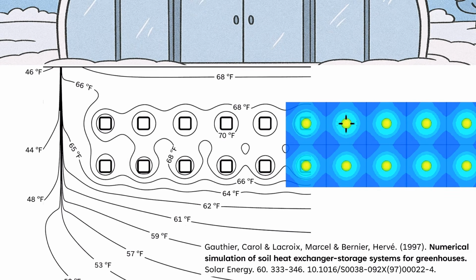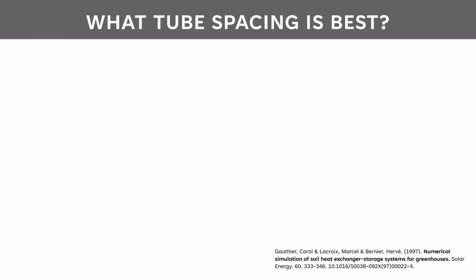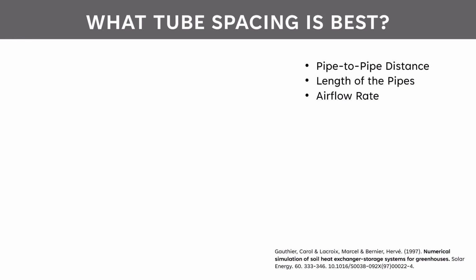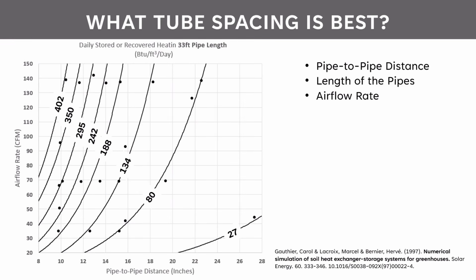This gives me a feel for the level of heat penetration into the soil from the heat exchanger. In their study, they ran 240 different simulations and validated them by comparing to a prior real-world prototype from 1990. They developed data providing a clear relationship between the pipe-to-pipe distance, the length of the pipes, and the airflow rates. As a result of the study, they produced this graph showing some of the trade-offs for a 33-foot long pipe. On the bottom axis, we have the pipe-to-pipe spacings from 8 to 28 inches. The vertical axis is the airflow rate through the pipes, and the numbered lines are the amount of daily stored heat. A key takeaway is how poor the wider spacings are. Not even increasing airflow can make up for it.